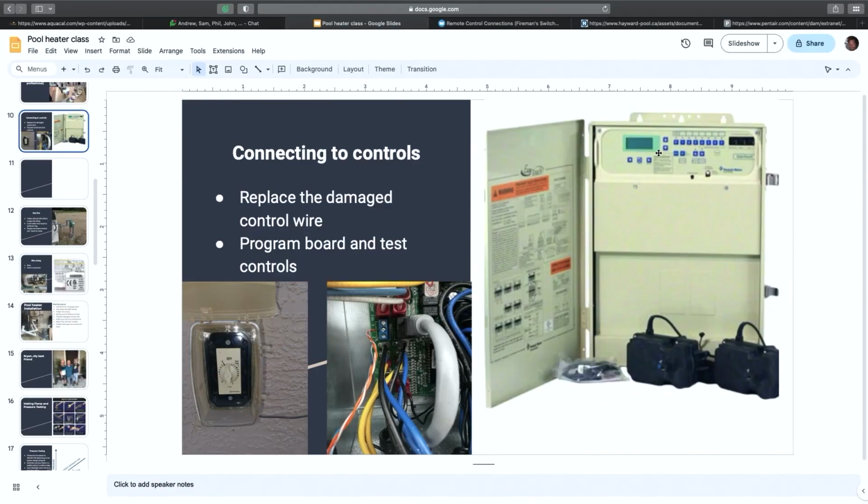Yeah, that's good. So right here, you can step out of auto mode, go into service mode, and turn on your stuff. One of the auxiliaries or the heater button should control your heater, right? Now, if you have a solar panel up on the roof, then one of the auxiliaries or the heater button is going to control the solar panel, and the other one will control the heater, which makes it all the more important that you put it back in auto mode and go find out how the customer is normally activating this heater.